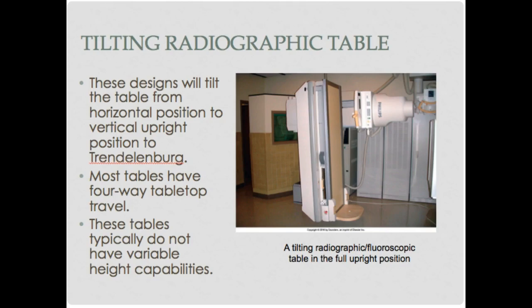For tilting radiographic tables — this is a fluoro table with the image intensifier and a footboard. These designs tilt the table from horizontal to vertical and to Trendelenburg. It'll go Trendelenburg about 15 degrees and can go to 45 or 90 degrees. I've usually worked on 15-degree Trendelenburg — head down — and then it goes to a full upright position. These tables typically do not have variable height capacities, so they don't raise and lower. There's a footboard that comes out, so if a patient can't get up, I stand it up and have them step on.